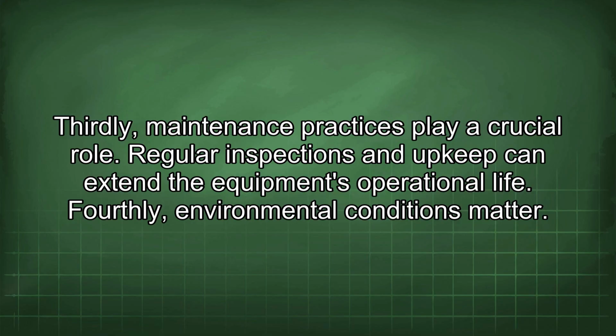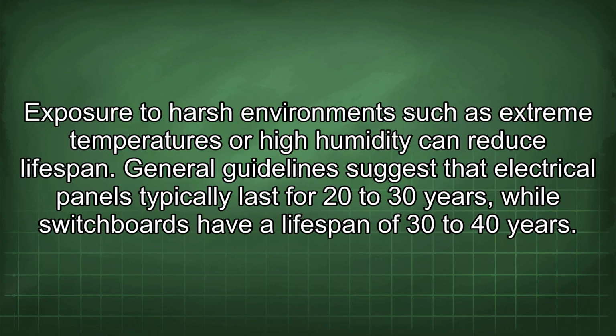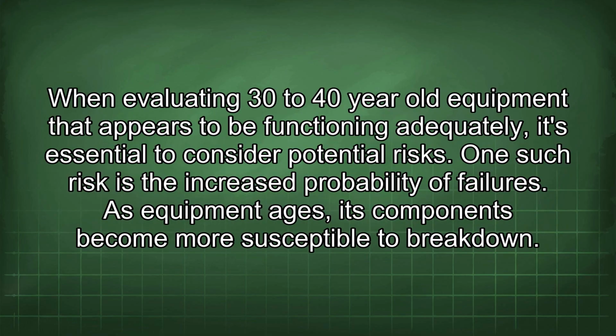Fourthly, environmental conditions matter. Exposure to harsh environments such as extreme temperatures or high humidity can reduce lifespan. General guidelines suggest that electrical panels typically last for 20 to 30 years, while switchboards have a lifespan of 30 to 40 years. When evaluating 30 to 40-year-old equipment that appears to be functioning adequately, it's essential to consider potential risks. One such risk is the increased probability of failures.